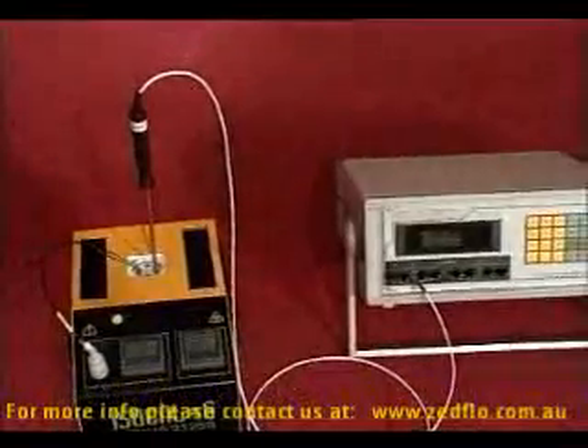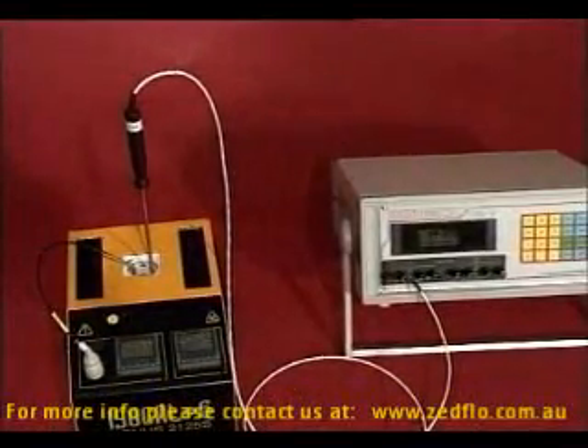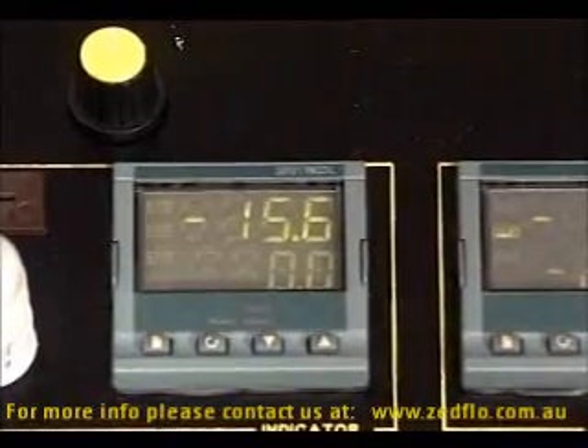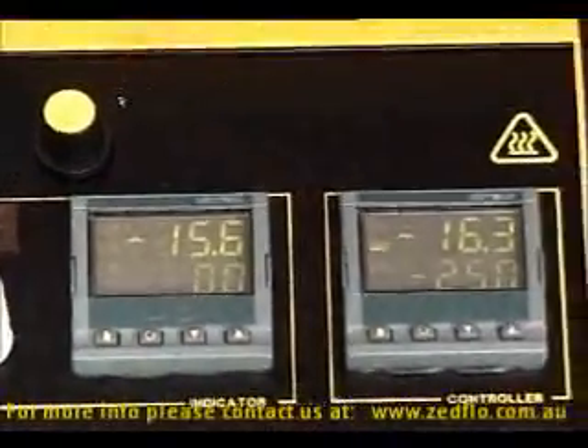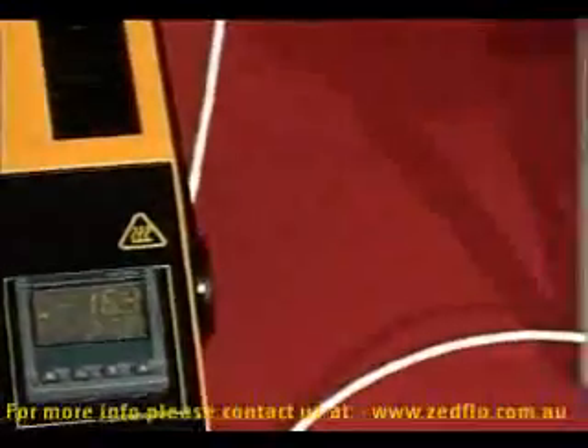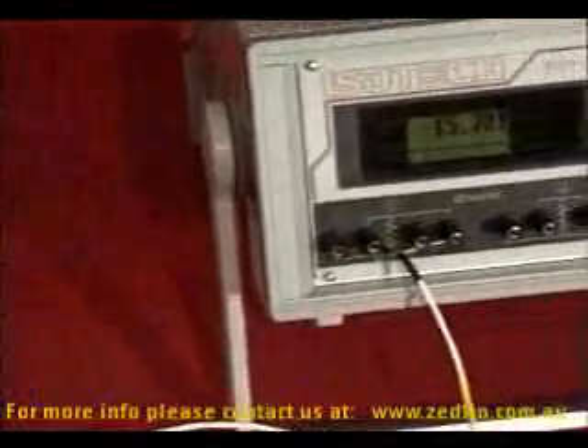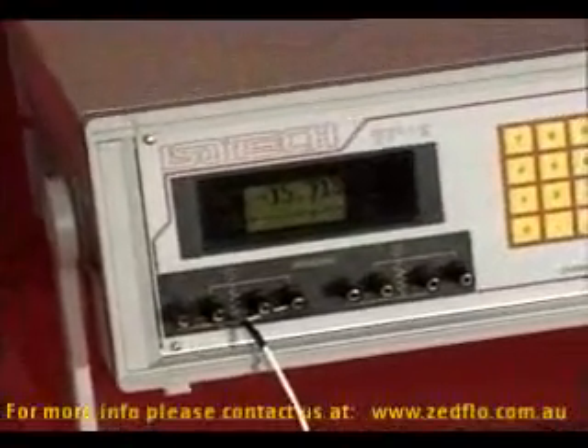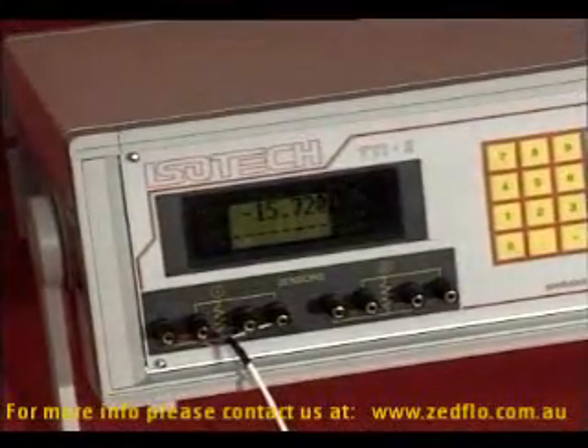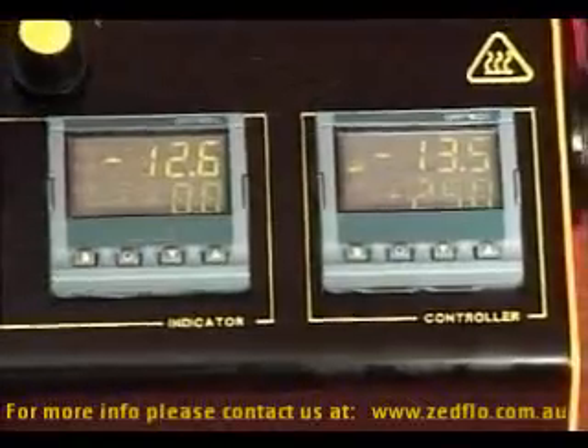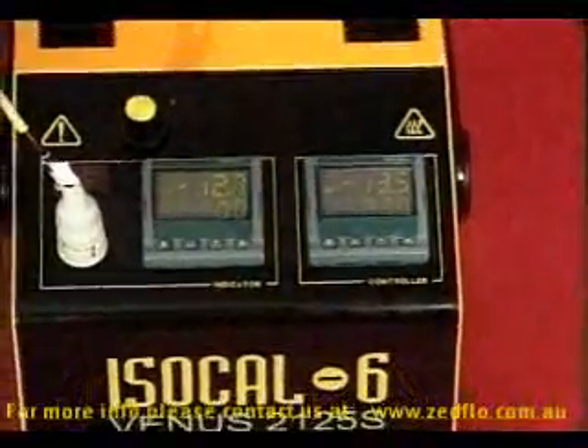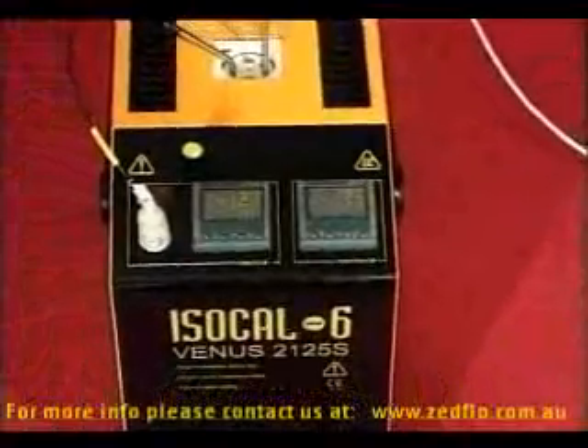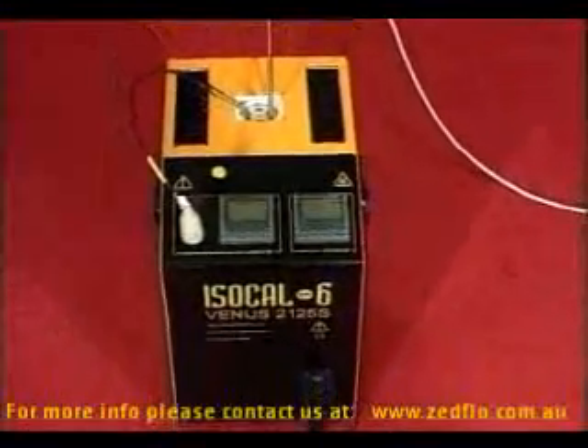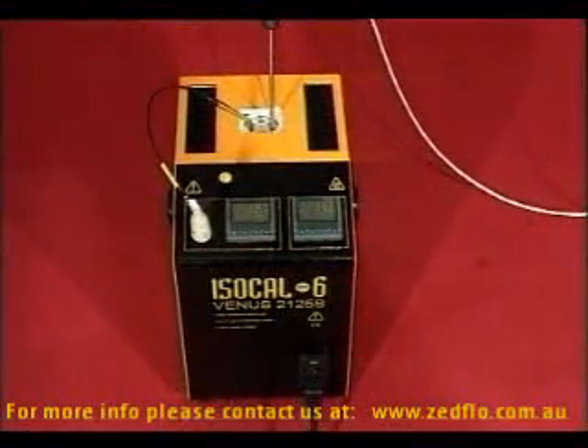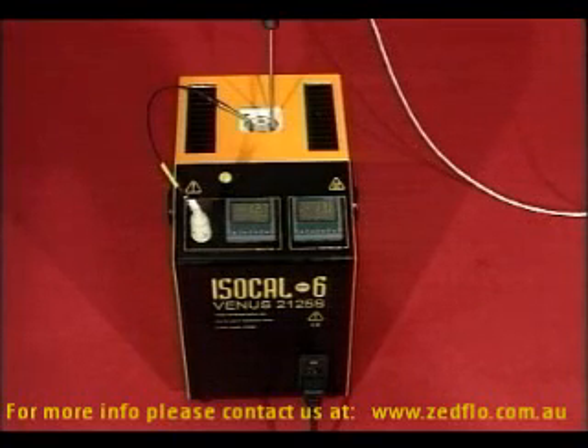The second standard, also placed in another of the 6 holes, is connected to a TTI-2 by this cable, and gives us a more accurate indication because the resolution of the small indicator is only 0.1 of a degree Celsius. Once the sensors in the insert are at a stable preset temperature, the industrial temperature sensors are compared to the working standard thermometer. This is called calibration by comparison. This illustrates a Venus setup as a metal block calibrator, comparing industrial temperature sensors to a working standard.